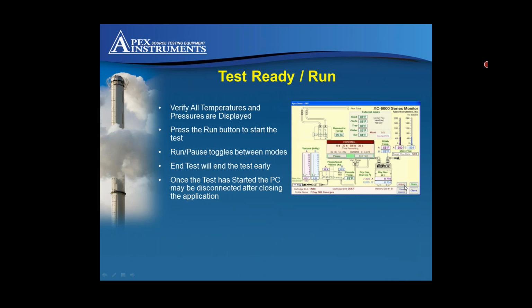The screen displays my flow rates, all my temperatures, my barometric pressure, vacuums, and valve positioning. The vacuum and valve positioner we'll talk about later when you start running longer runs. You start getting some buildup on your traps, your vacuums will start to go up, and your valves start opening more, until it gets to a point where it can't sample any longer. That's when you'd want to stop your test. If you set any alarms against any of these items, they'll be flashing red on the screen.